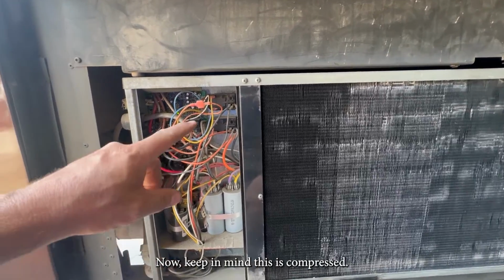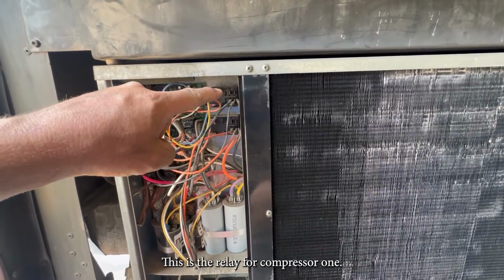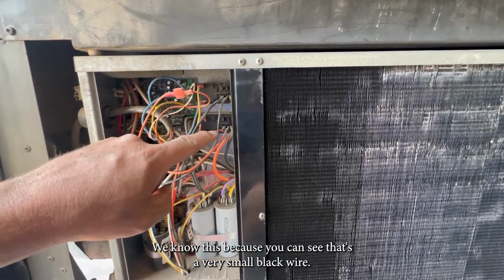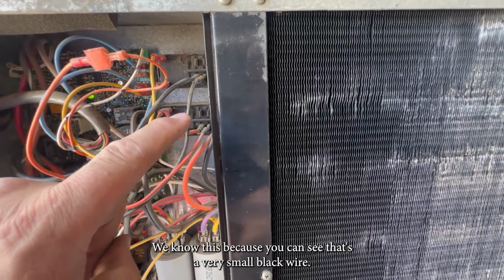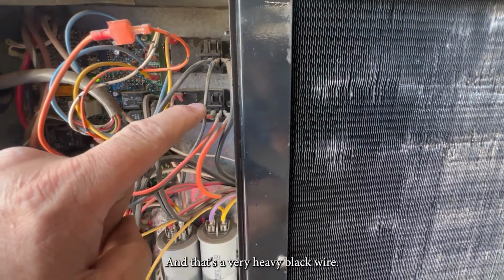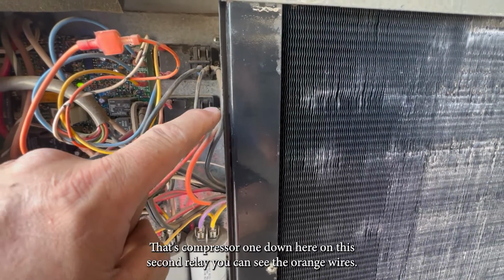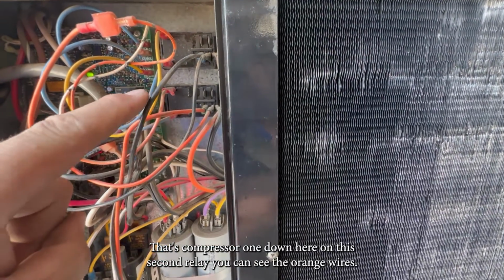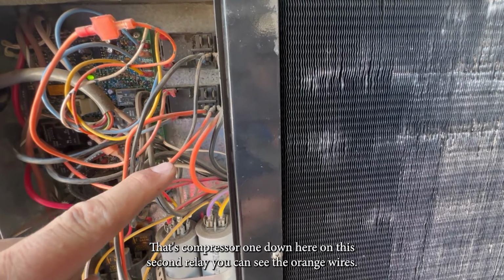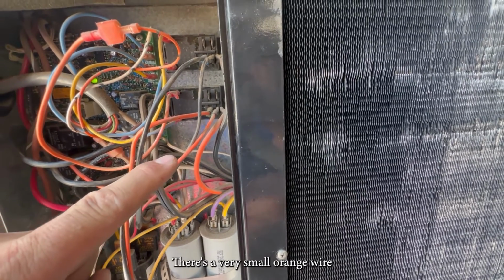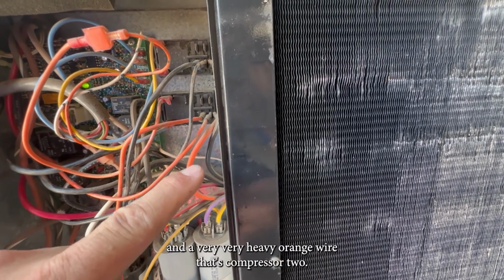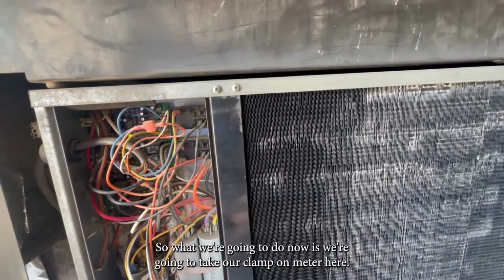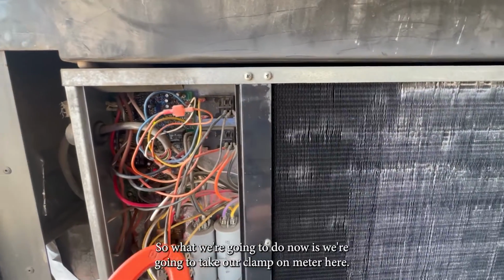Now, keep in mind, this is the relay for compressor 1. We know this because you can see that's a very small black wire and that's a very heavy black wire. That's compressor 1. Down here on the second relay, you can see the orange wires. There's a very small orange wire and a very heavy orange wire. That's compressor 2.